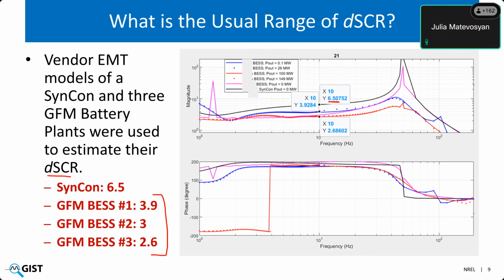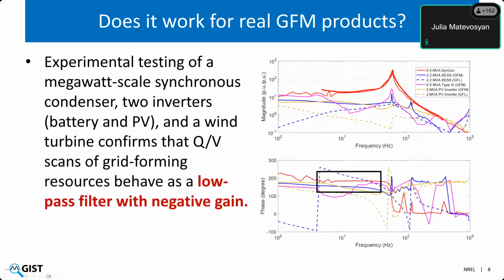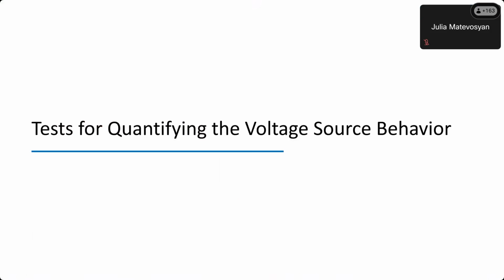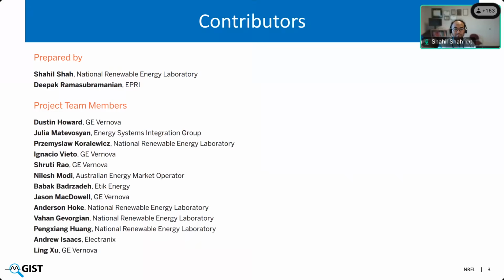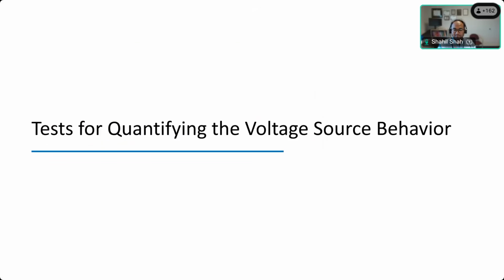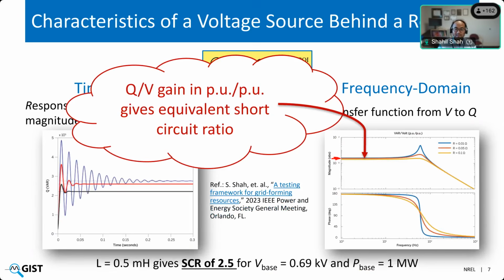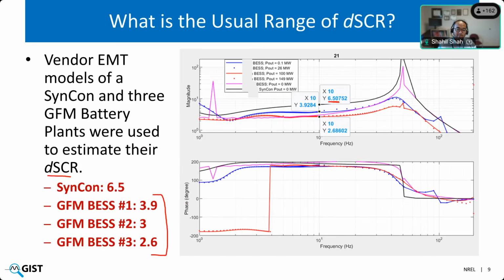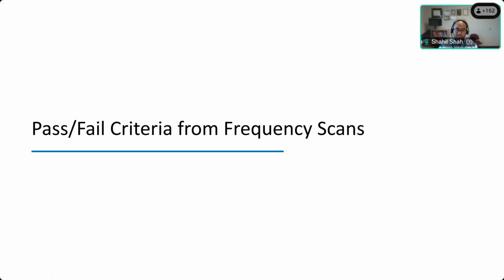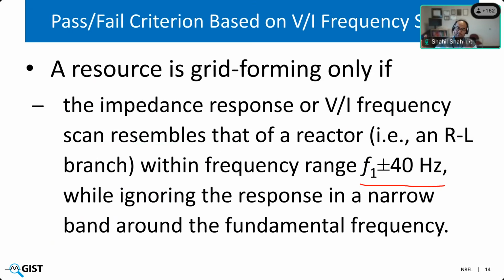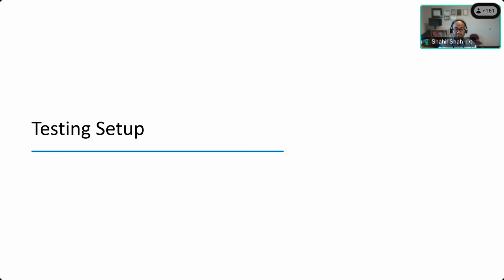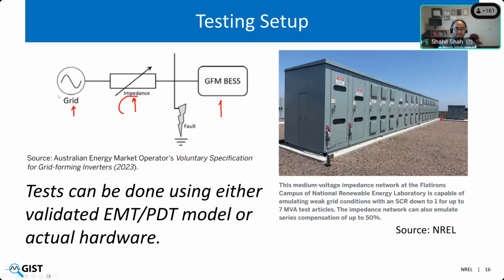The next one is the size of the phase jump related to the grid voltage behind the impedance or the voltage at the POI? In this particular report, we have used the grid voltage phase jump because I think it is very hard to have the exact phase jump at the POI, particularly if you have some impedance between the ideal voltage source and the POI when you're emulating certain weak grid conditions. So the phase jump is applied within this ideal voltage source.